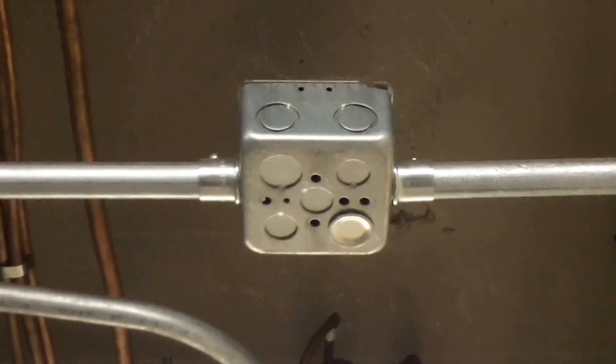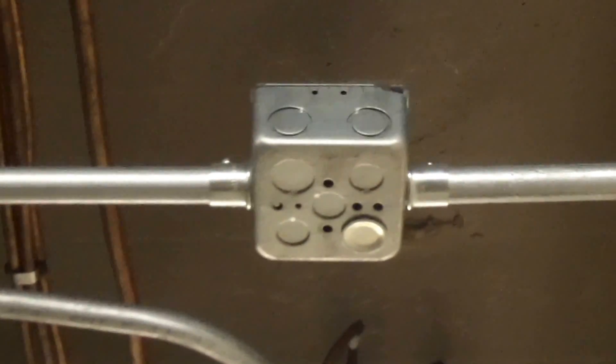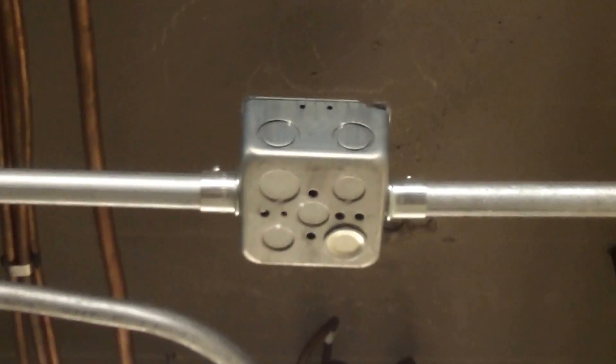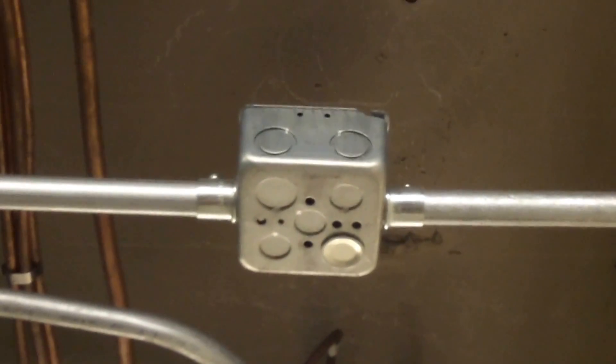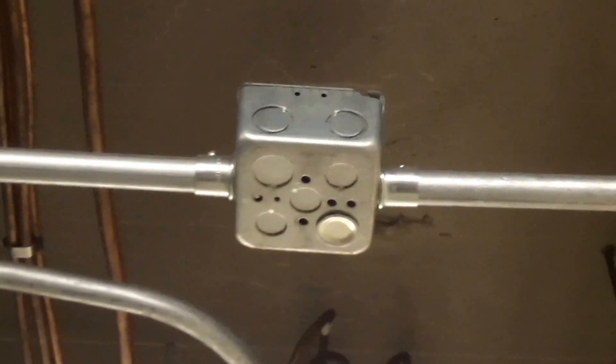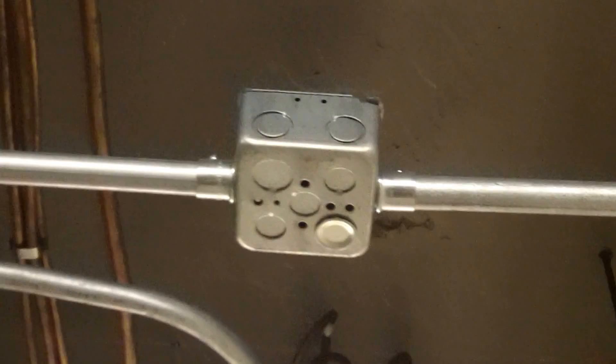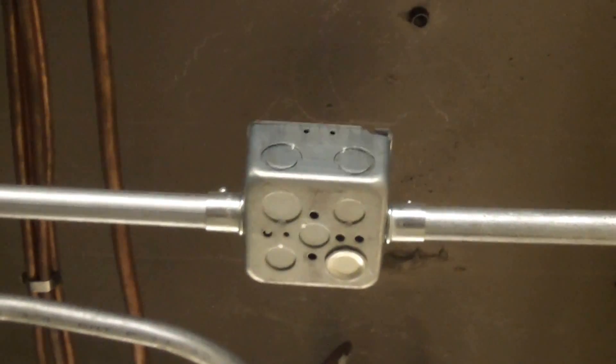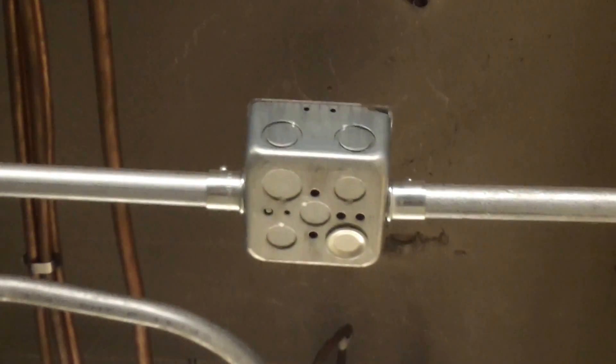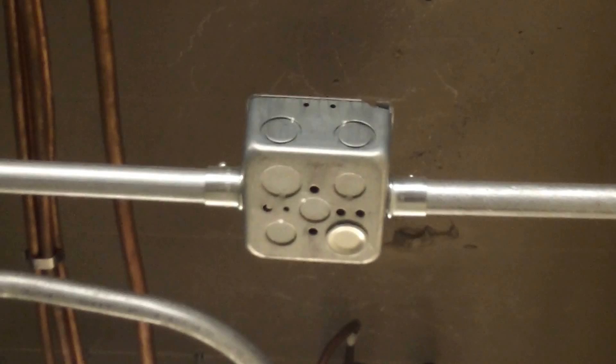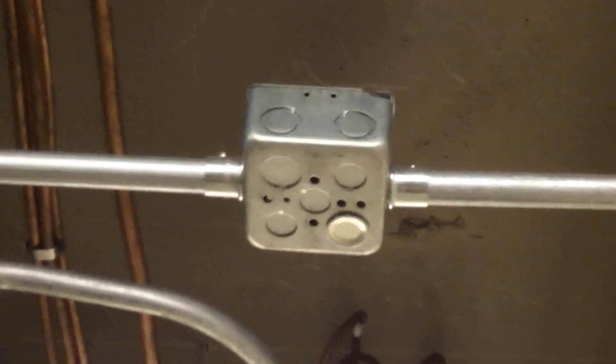And then the conduit has to be secured within three feet on each side of the enclosure. Or if the raceways were to come in both on the same side, then you would secure the raceways within 18 inches. And in that case, the raceways could actually support the box, but not in this case.